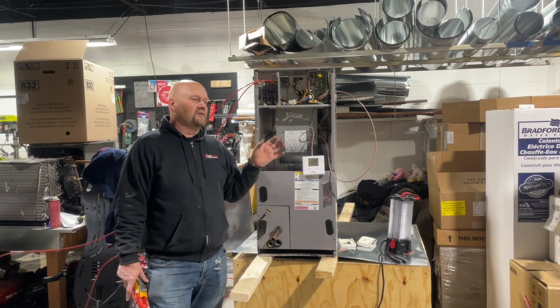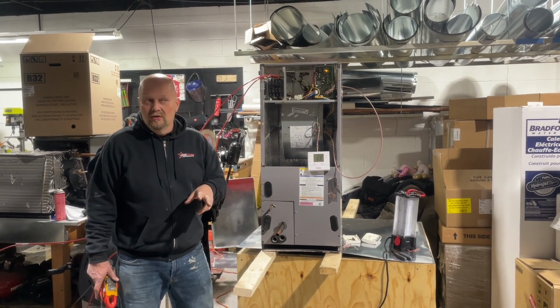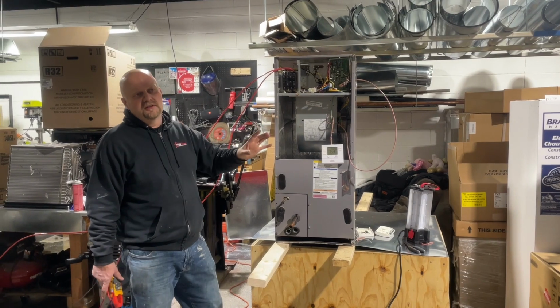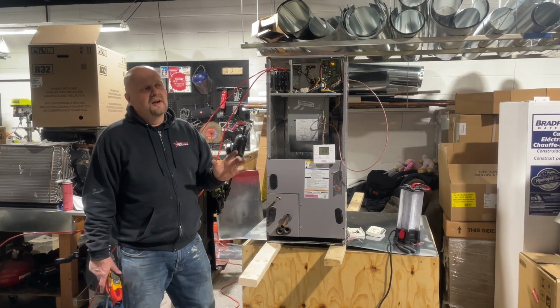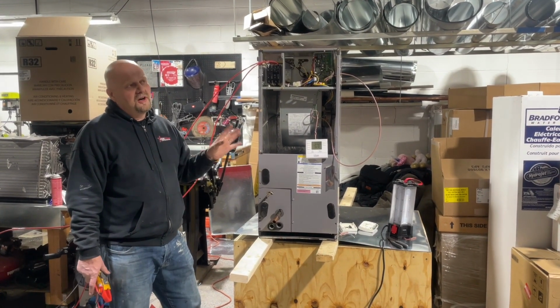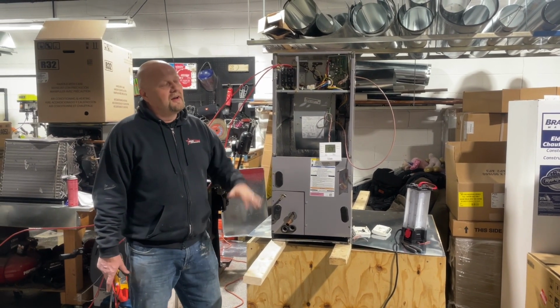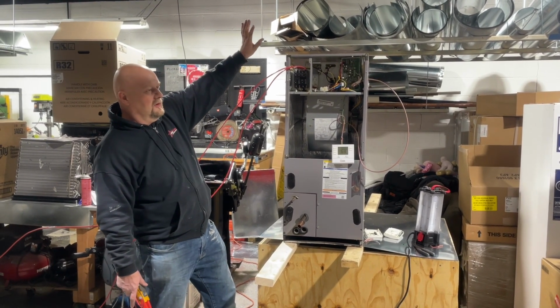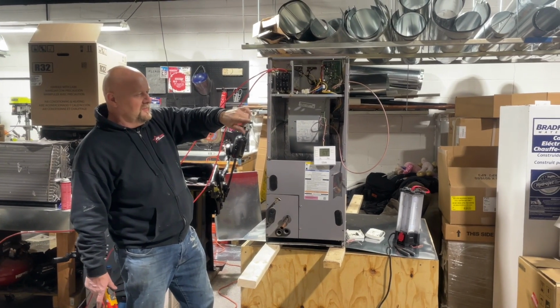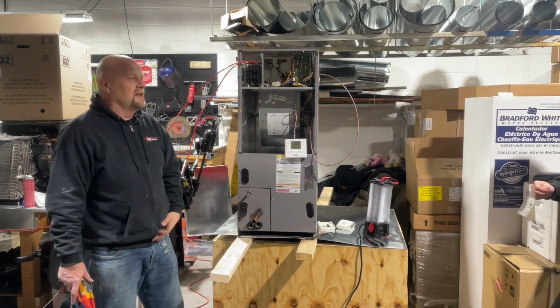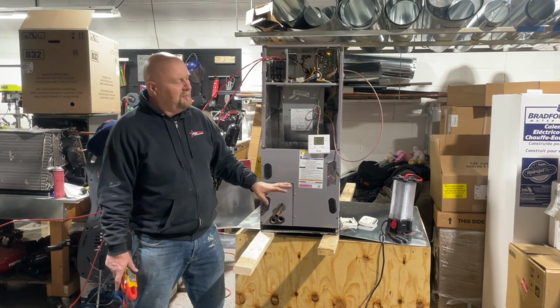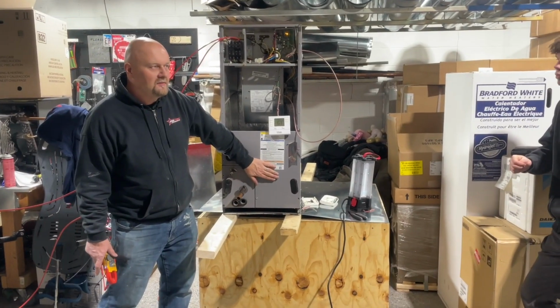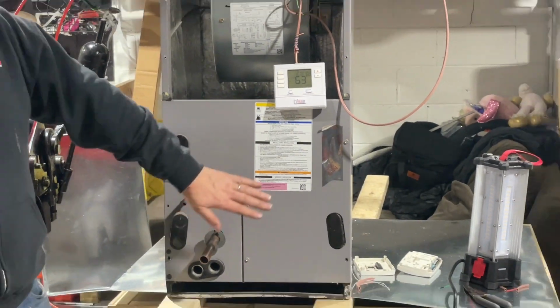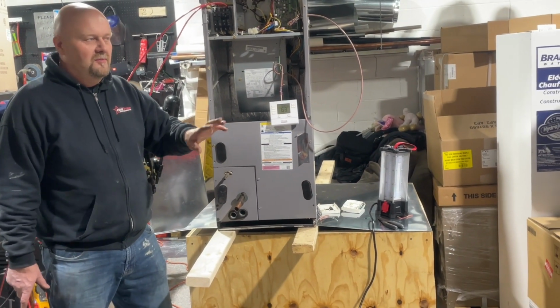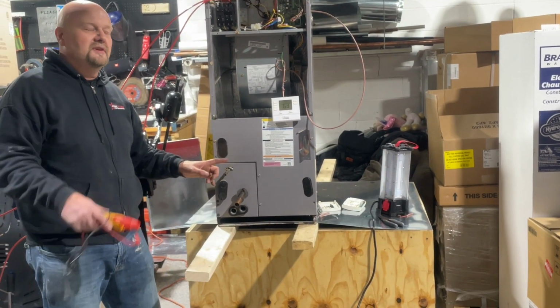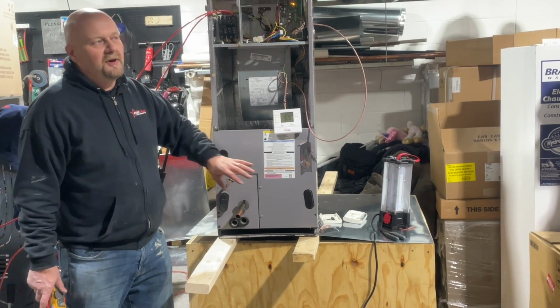But when you have an electric furnace or you have a Unico with the electric section in the front, you can run both the heat pump and the electric section at the same time, because the coil is behind the blower and electric heat is on the other side of the blower. Do you understand? No. So this is very important to understand. When the heat pump heats up, this is the part that gets hot, right? And you run refrigerant through it at X temperatures. Because you basically reverse the flow of refrigerant, this becomes a condenser. This is the part that discharges the heat.